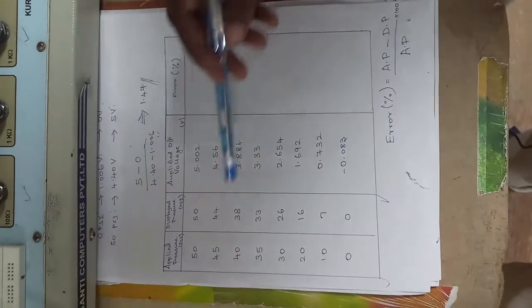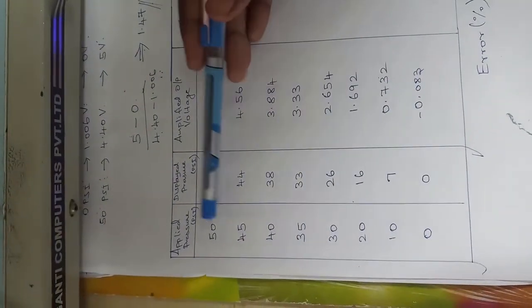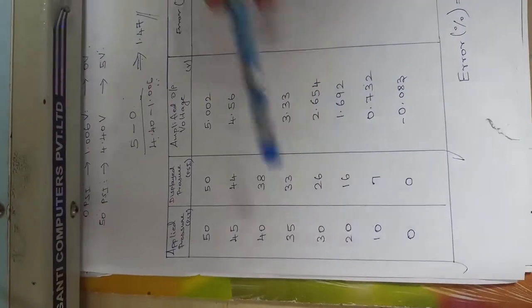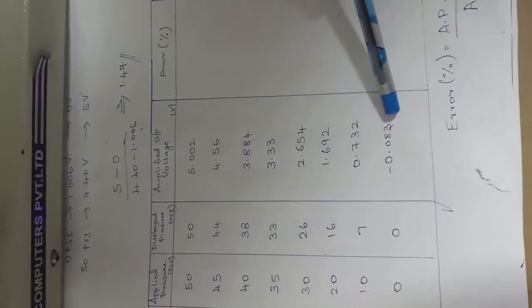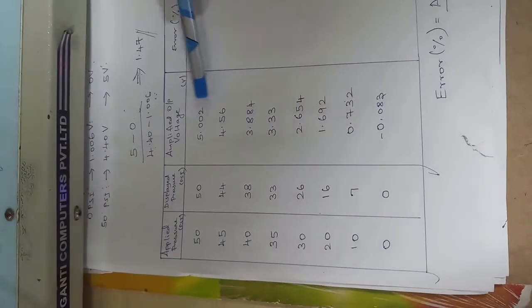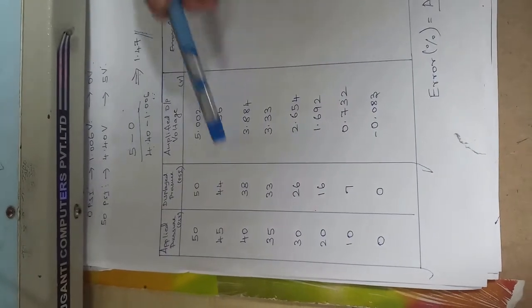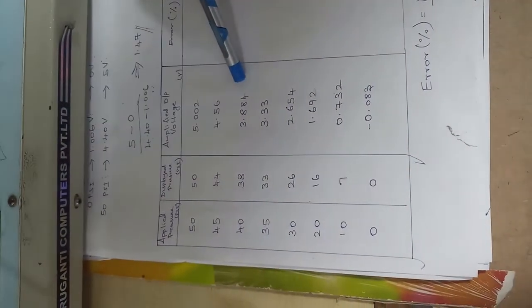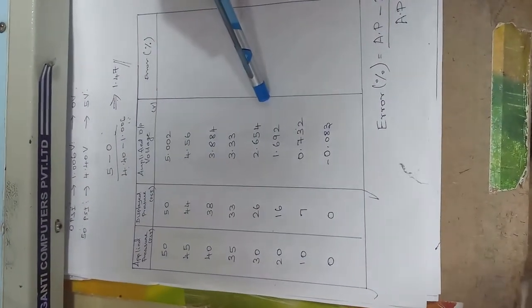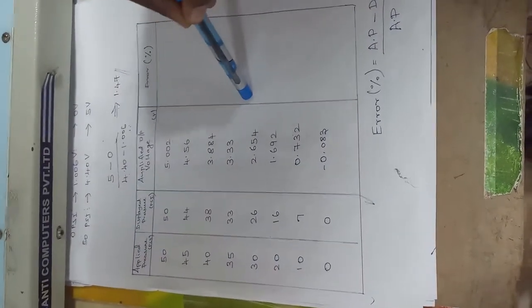These are the values we got. The applied pressures were 50, 45, 40, 35, 30 psi, and I got corresponding voltage values. For 50 psi, I set it to 5.002 volts; for 45 psi, I got 4.56 volts; for 40 psi, I got 3.884 volts, and so on. These values contain error because the pressure sensor is leaking and instrumentation error is also present.